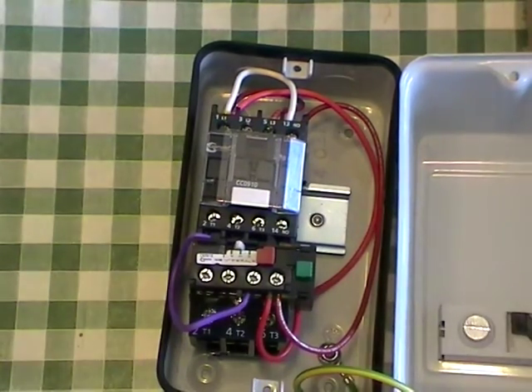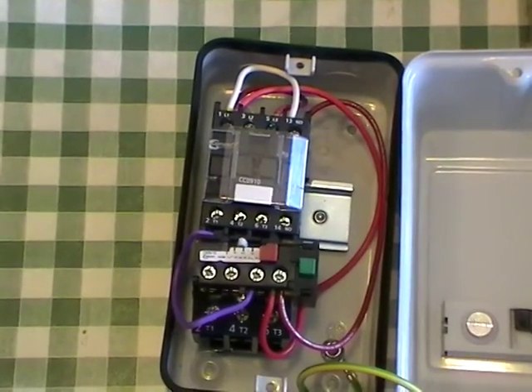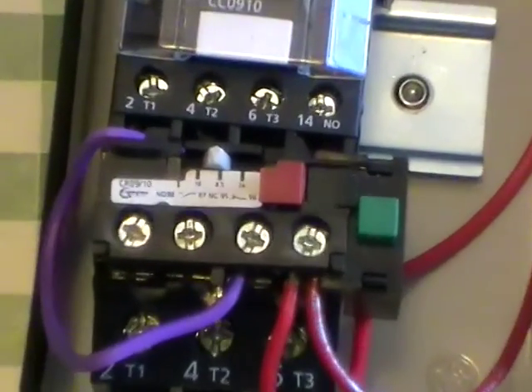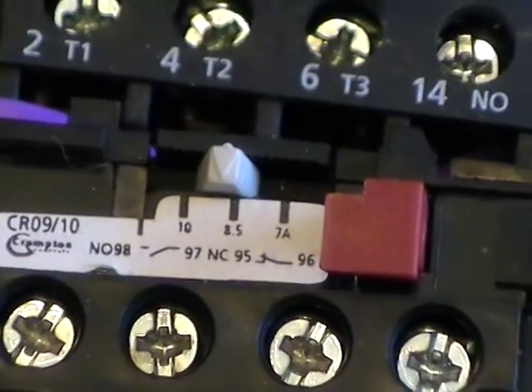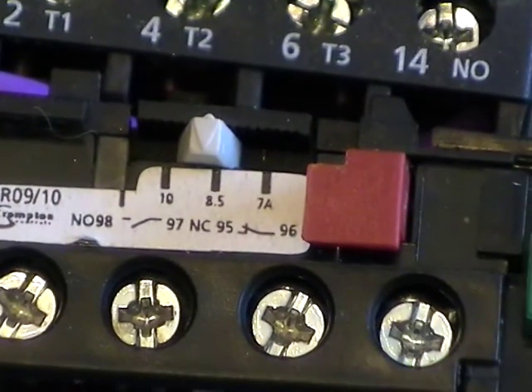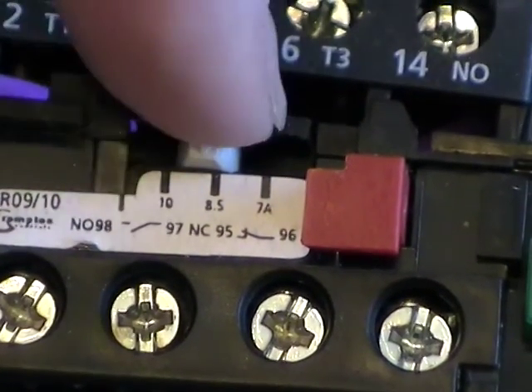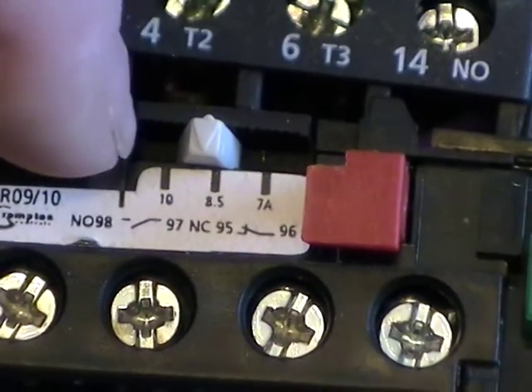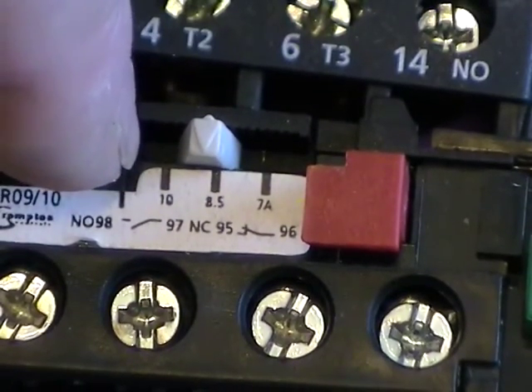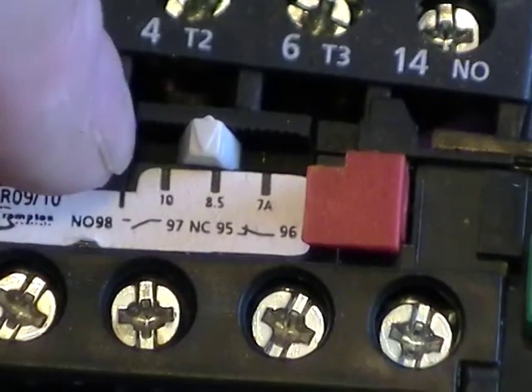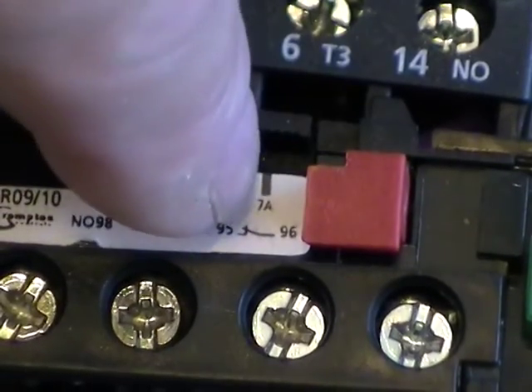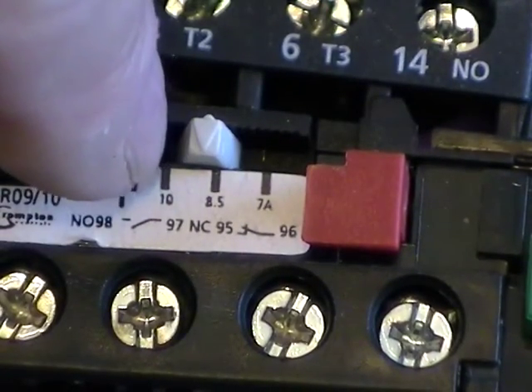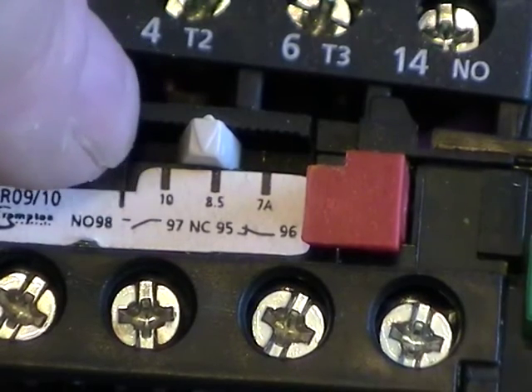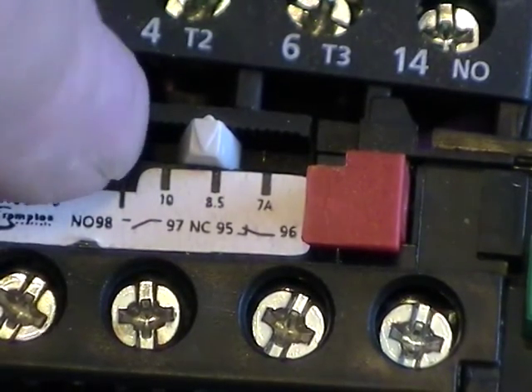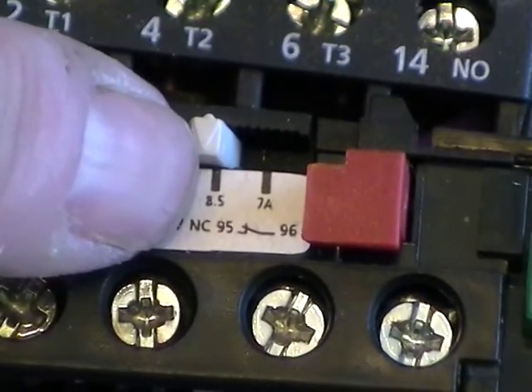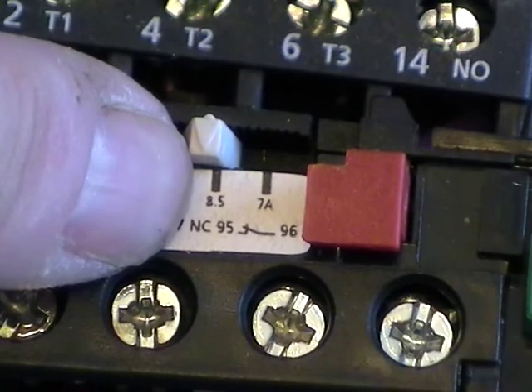If I zoom down on this, there is this white tab here which slides back and forth to set the current trip value from, on this case, between 7 amps and 10 amps. As my generator is rated 8.8 amps, I've got the mark just fractionally above 8.5.